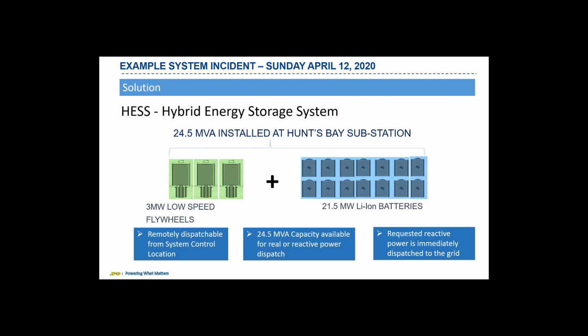This is where the energy storage system comes in. The details are that it has a 24.5 MVA capacity. This capacity is available for both real power or reactive power, as long as you don't exceed the total MVA capacity. In terms of real power, the breakdown is 21.5 megawatts from batteries and 3 megawatts from the flywheel. The main feature that helped us in this particular situation is that the storage is remotely controllable by the operators in the control room. So they see the grid event, they see the current situation, and they want to remedy it.